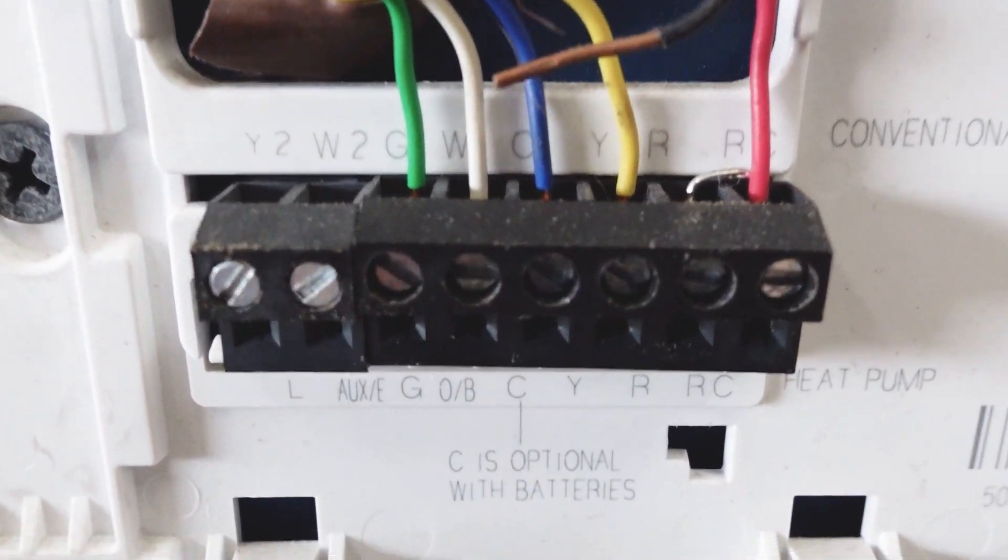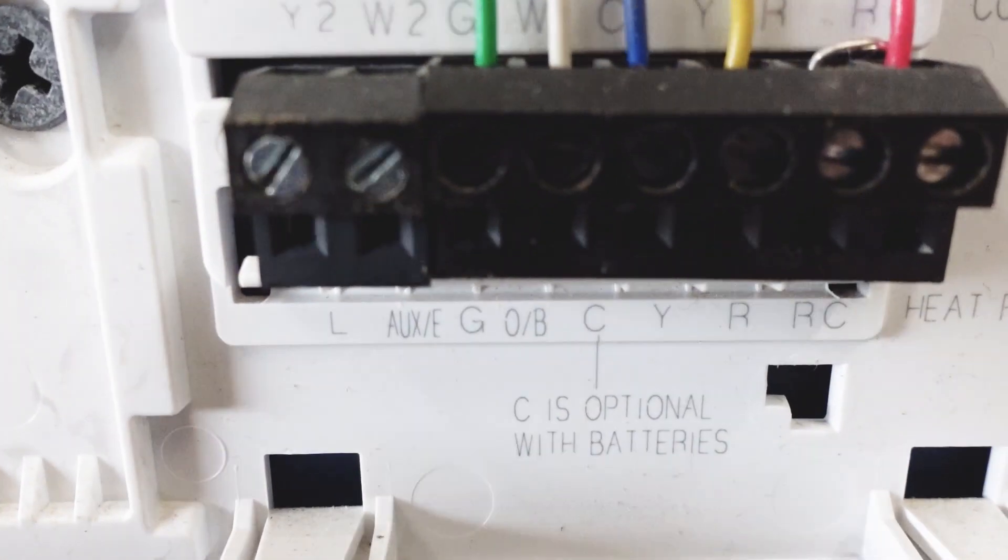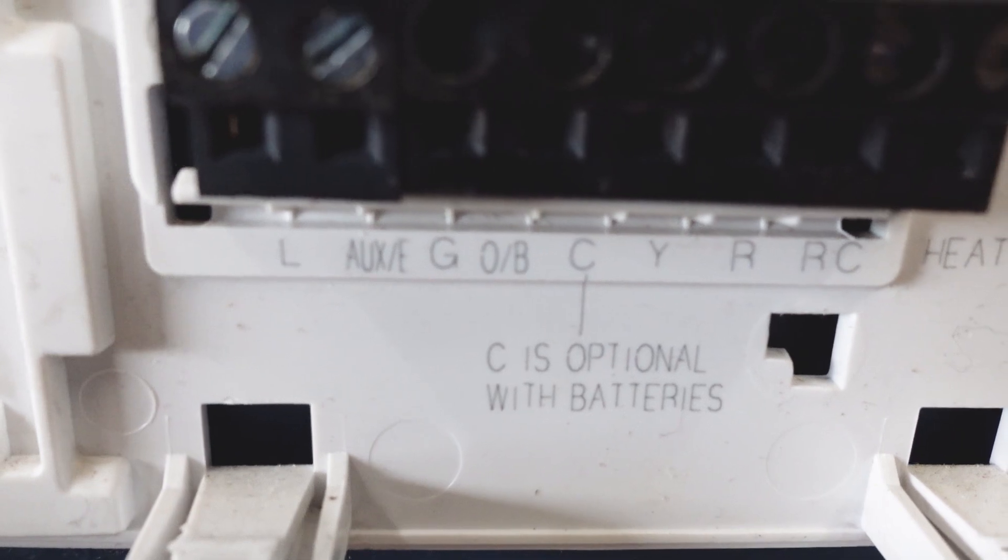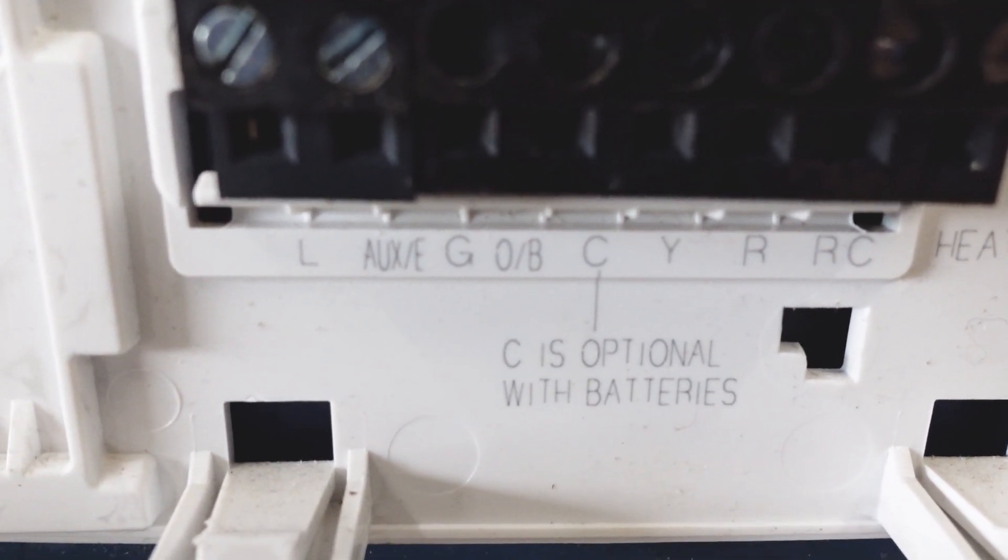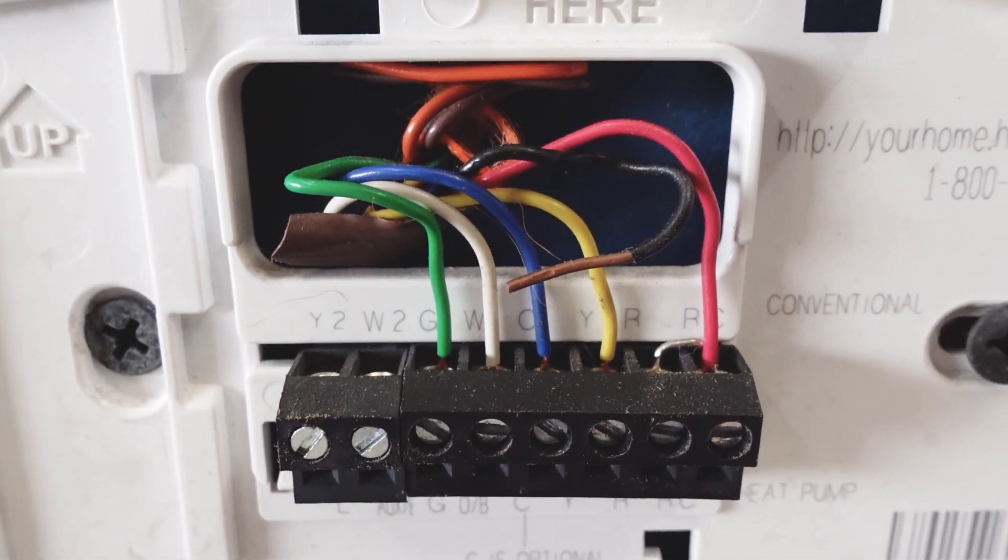Some people will accidentally connect it to the heat pump B terminal. The B terminal is not common, but rather it's for heat pump systems that energize the reversing valve in heating mode rather than cooling mode and is a common mistake that people make when connecting a thermostat.